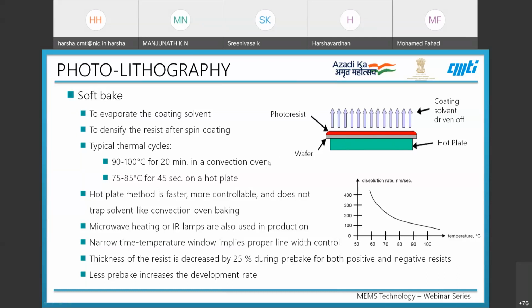Typical thermal cycles for soft bake vary from 90 to 100 degrees for 20 minutes in a convection oven, or 75 to 85 degrees for about 45 seconds on a hot plate. The hot plate method is much faster and more controllable, and it does not trap solvent like convection oven baking.